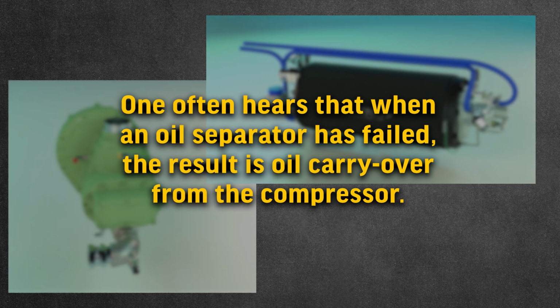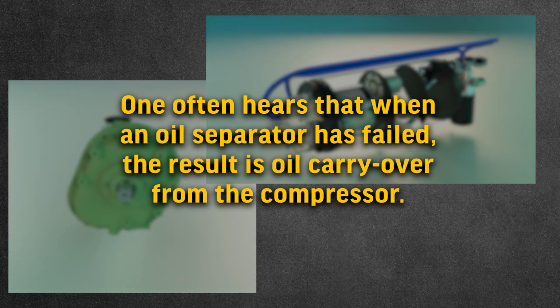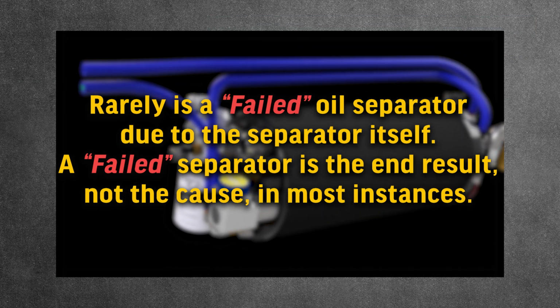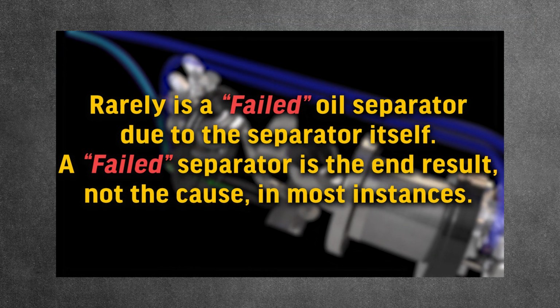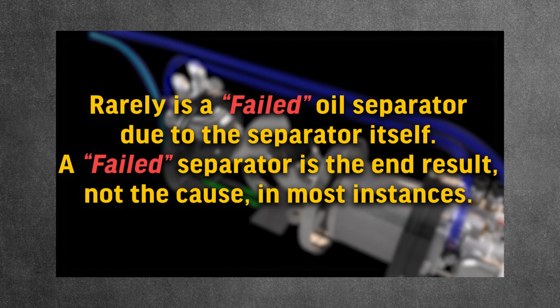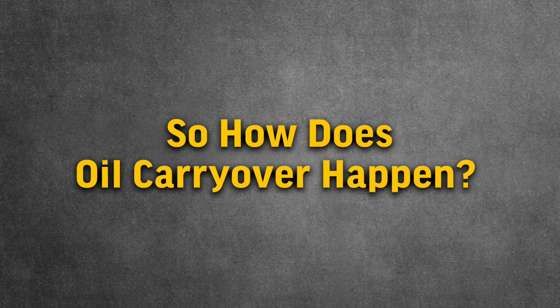One often hears that when an oil separator has failed, the result is oil carryover from the compressor. Rarely is a failed oil separator due to the separator itself, and a failed separator is the end result, not the cause in most instances. So how does oil carryover happen?